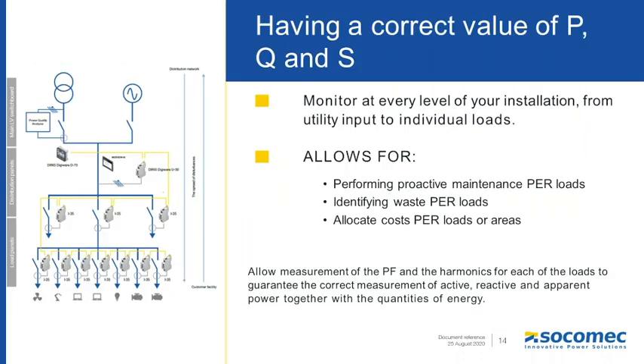The second key factor we will look at is having correct values at each level of the installation. Power monitoring can be performed at different levels of the installation. However, if the power monitoring is done only at a single location, the value might be distorted and won't be usable for good analysis and follow-up actions. It's important to have power monitoring analysis per load in order to understand power quality issues at every level, so you can distinguish the loads that are creating problems: VFDs, motors, power electronics, lighting, and so you can perform actions per equipment. If the loads are individually monitored, then you can perform also proactive maintenance by load. You can look at the waste by load.